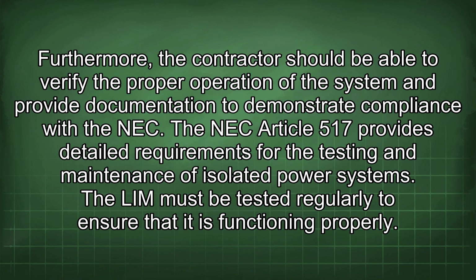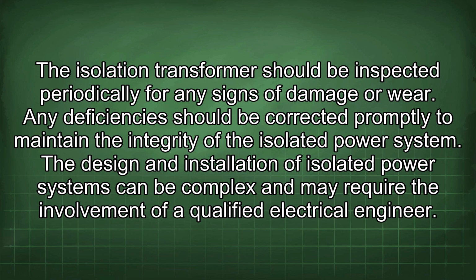with the NEC. The NEC Article 517 provides detailed requirements for the testing and maintenance of isolated power systems. The LIM must be tested regularly to ensure that it is functioning properly. The isolation transformer should be inspected periodically for any signs of damage or wear. Any deficiencies should be corrected promptly to maintain the integrity of the isolated power system.